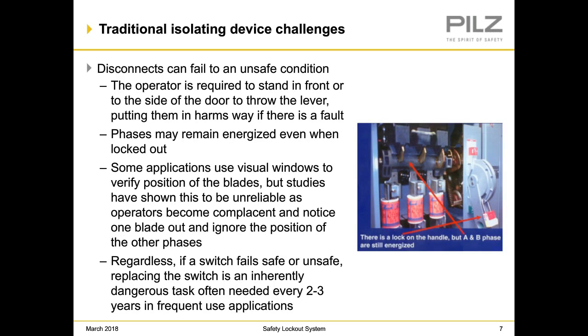Disconnects, as we just mentioned, can fail to an unsafe condition. The operator is required to stand in front or to the side of the door to throw the lever, putting them in harm's way if there's a fault. Phases may remain energized even when locked out. As you can see in the picture, there's a lock on the handle, but A and B phase are still energized. So some applications use a visual window to verify the position of the blades. But studies have shown this to be unreliable as operators become complacent and subconsciously notice one blade out and ignore the position of the other phases.